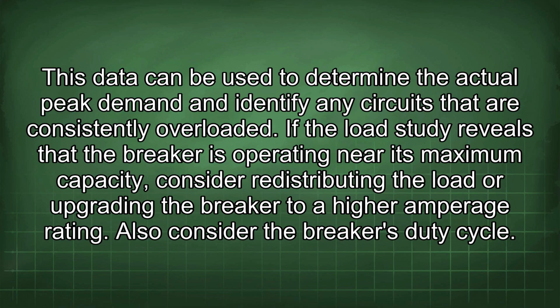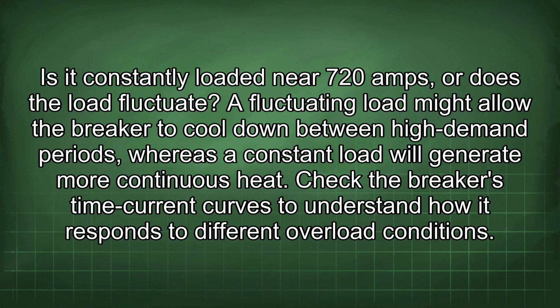If the load study reveals that the breaker is operating near its maximum capacity, consider redistributing the load or upgrading the breaker to a higher amperage rating. Also consider the breaker's duty cycle. Is it constantly loaded near 720 amps, or does the load fluctuate?